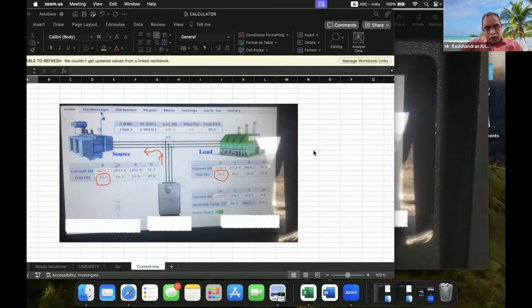And if you consider the passive filter as a tuned one, definitely it is a problematic one because it is tuned to a particular frequency. But if we design wide spectrum broadband filters, the filter can sweep all the harmonic frequencies like 5th, 7th, 9th, and 11th. So the passive filter also gives high performance, and it can be designed accordingly even for highly dynamic, variable loads. Here, for induction furnaces, many furnaces up to 3000 kilowatt have installed passive filters, and they are performing well.